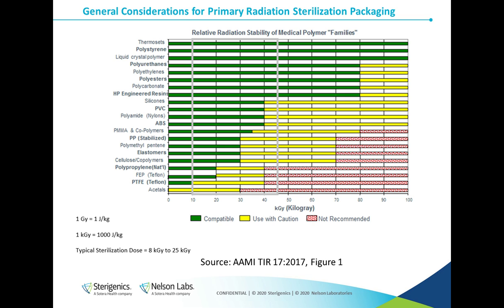This slide depicts the relative radiation stability of medical polymer families. This chart comes directly from AAMI TIR 17. As you look at the chart, the longer the green bar for a particular polymer, the more stable it is with respect to the radiation process. And you can see at the top of the chart, there are polymers like polystyrene and polyester, which have very long green bars, up to perhaps 100 kilograys.